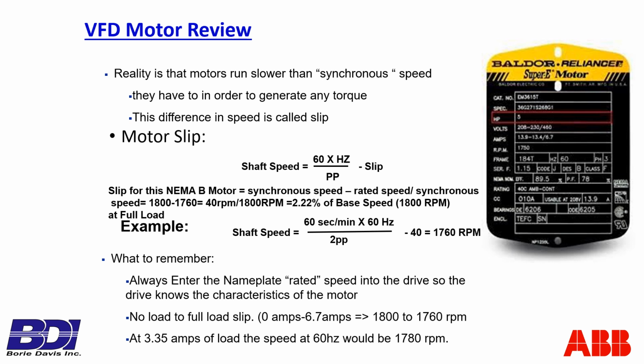To calculate the shaft speed of the motor, it would be the 60 seconds per minute times the frequency, in this case the nameplate frequency of 60 hertz, divided by the number of pole pairs, minus the slip. For a NEMA B design, the synchronous speed minus the rated speed, divided by the synchronous speed, would be the equation. In our case, the motor we've been talking about today is an 1,800 RPM base speed motor, but the nameplate says it's 1760. So do the math on that, you get 40 RPMs as the difference, the slip. And if you divide that slip RPM difference by the base speed RPM, you come up with a percentage of base speed as slip. So that's how you come up with that.